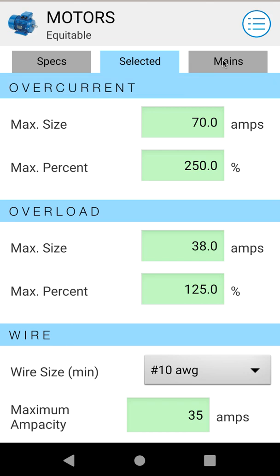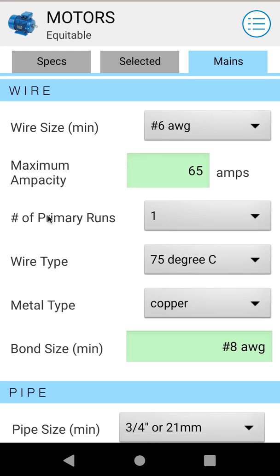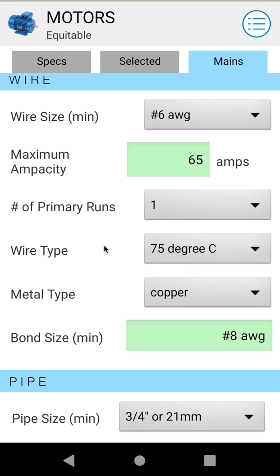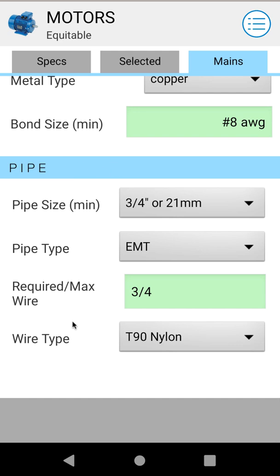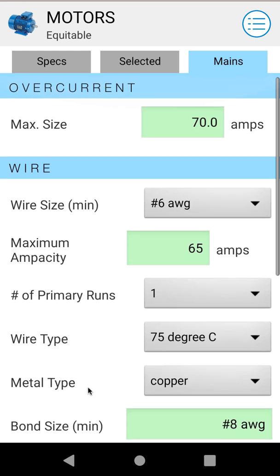The Mains tab works in pretty much the same way. We're getting a warning because we only have one motor selected, but when you have a group of motors selected, this tab will show your overcurrent for your main wires feeding that group of motors, your wire sizing for the main feeders, and conduit sizing for that entire group — not for each individual motor.